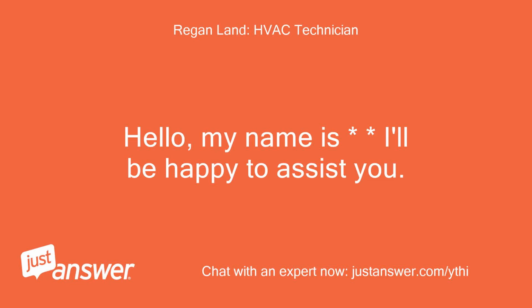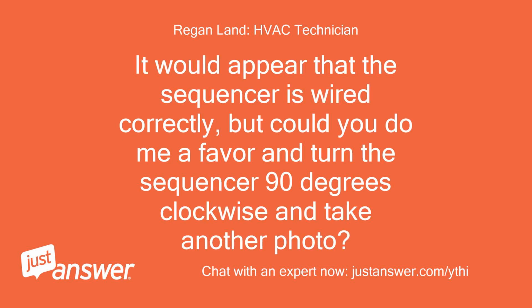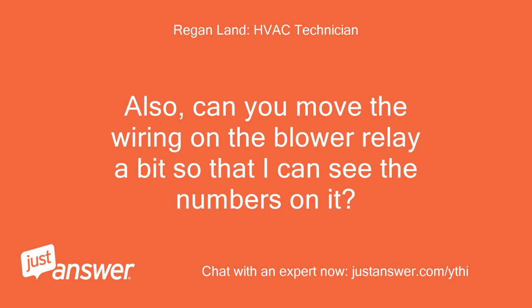Hello, I'll be happy to assist you. It would appear that the sequencer is wired correctly, but could you do me a favor and turn the sequencer 90 degrees clockwise and take another photo? Also, can you move the wiring on the blower relay a bit so that I can see the numbers on it?